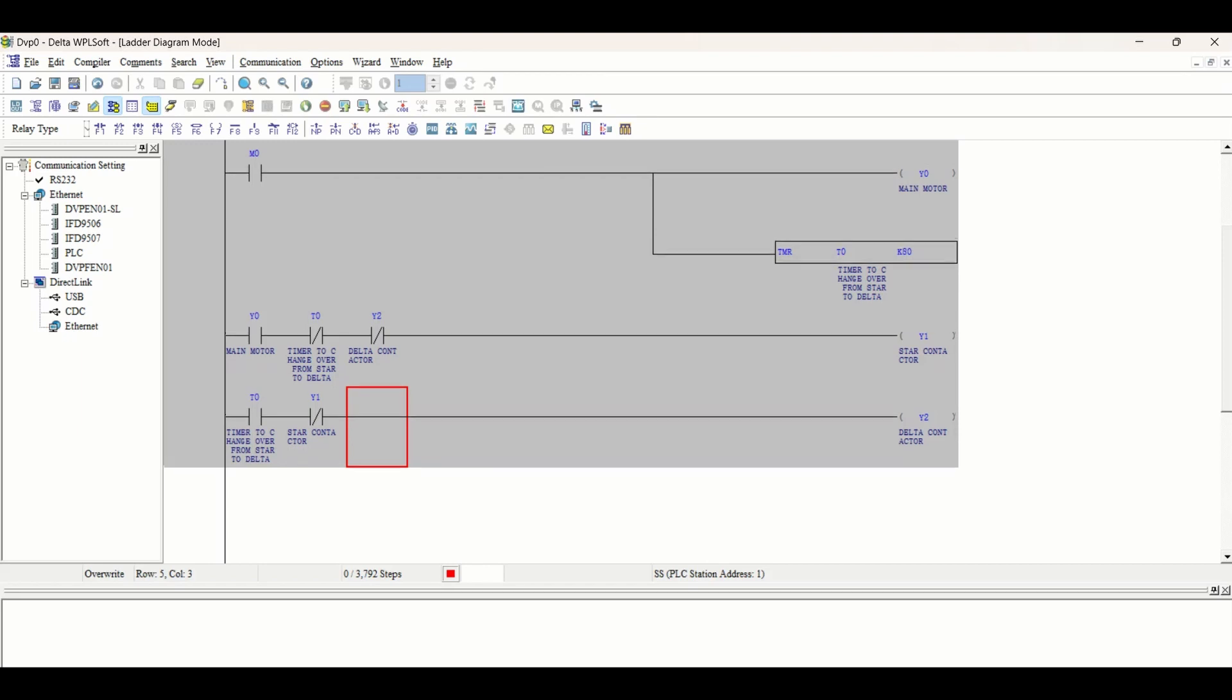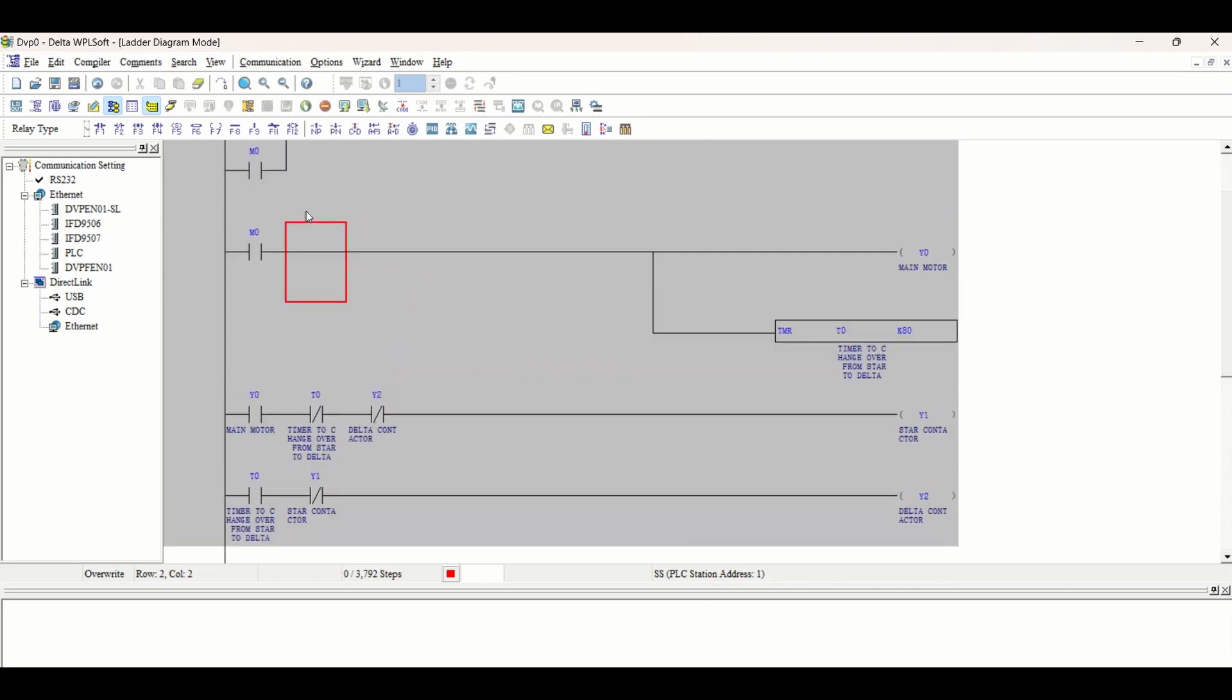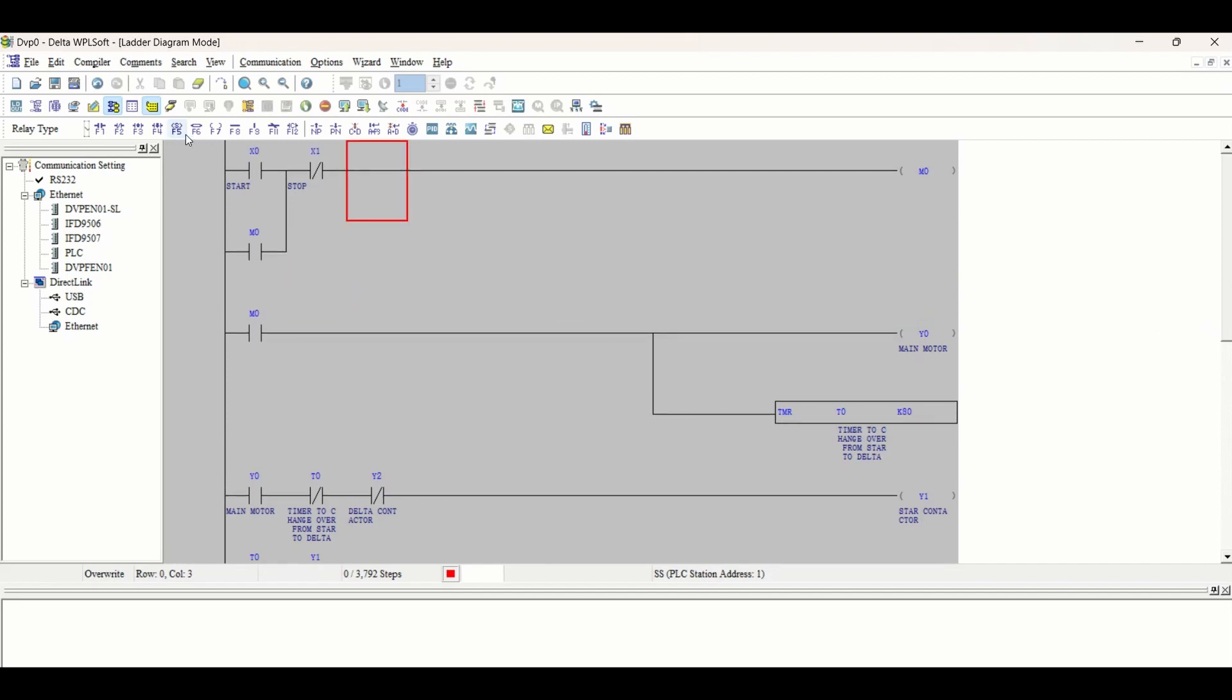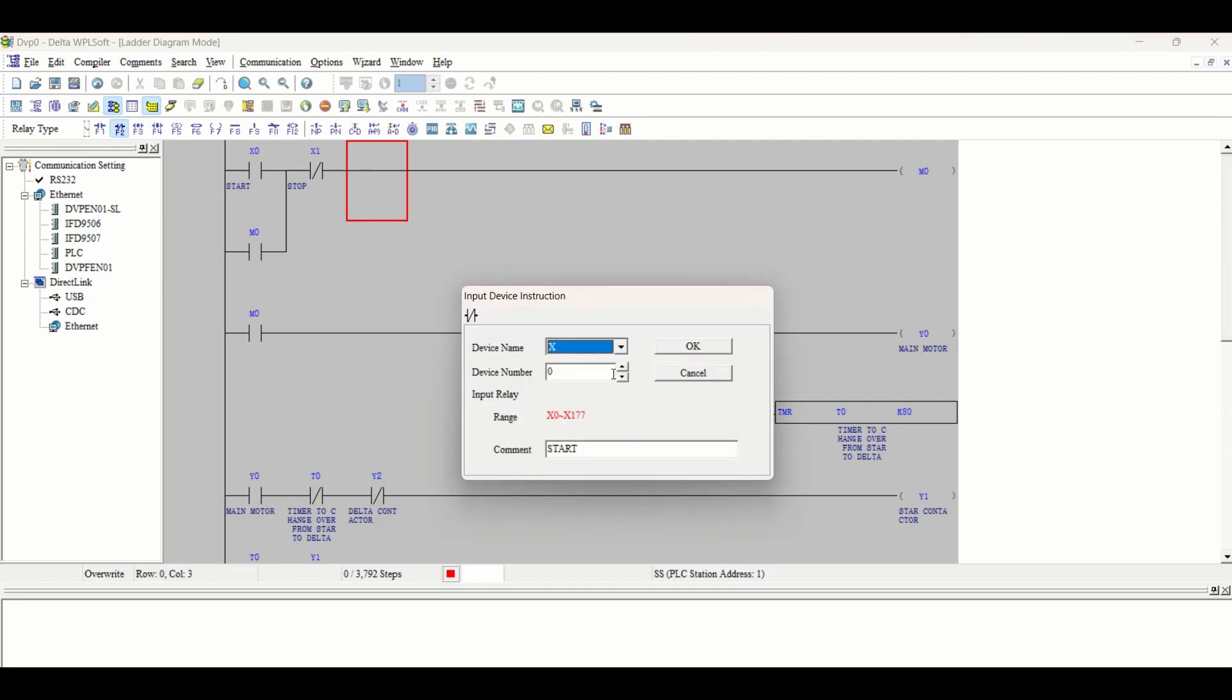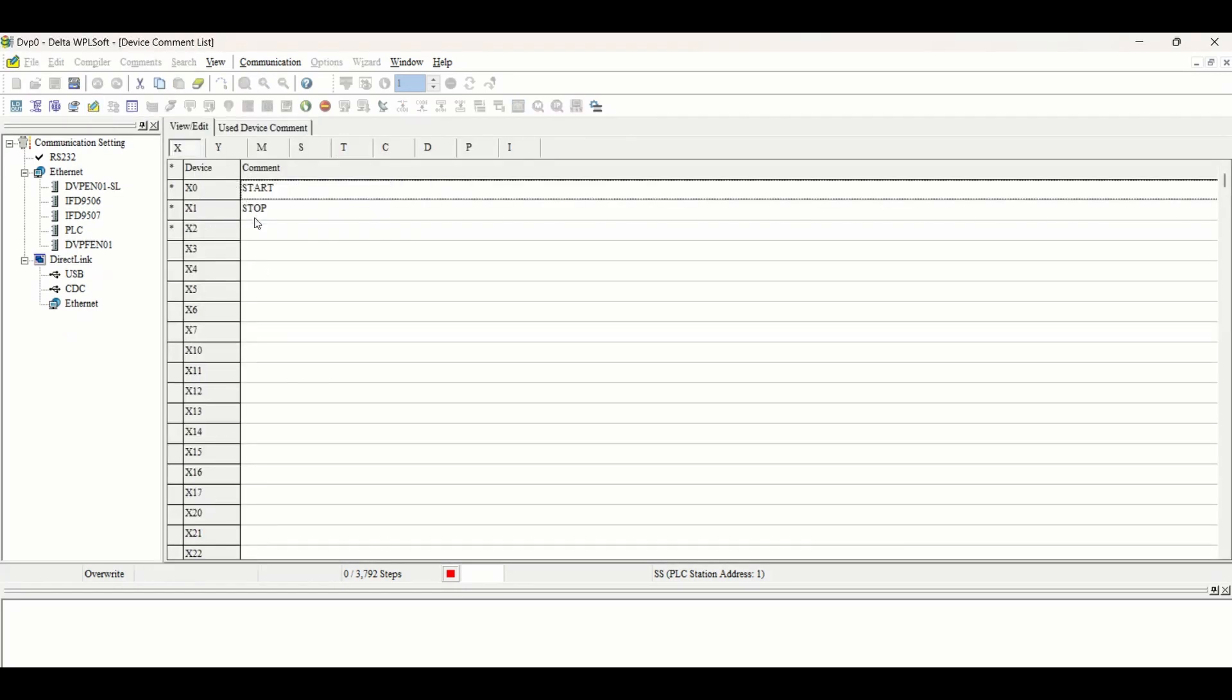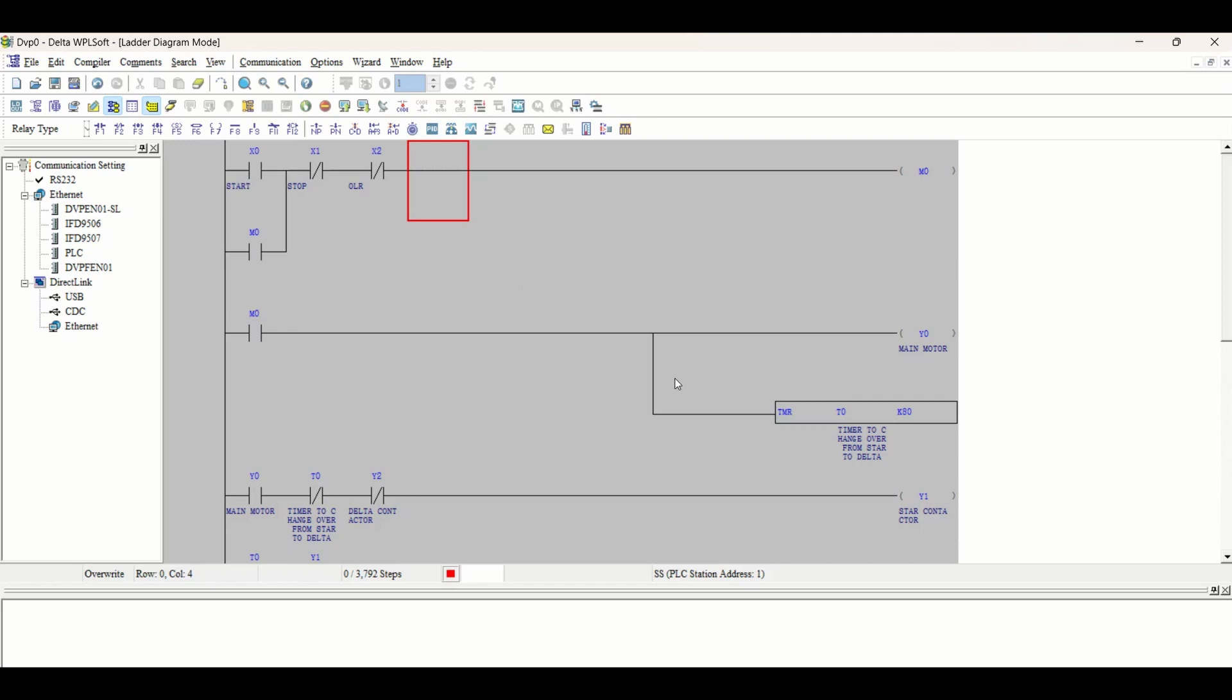There is also an OLR overload relay. The motor should not start or the current going to the motor should not be very high, so we are taking an interlock of OLR also. If OLR goes high, the motor should stop. We're taking the NC of OLR as X2. If the current becomes very high, it will cut off this circuit, M0 will turn off which will stop this output, the timer, and the whole circuit will stop. It's a protection.